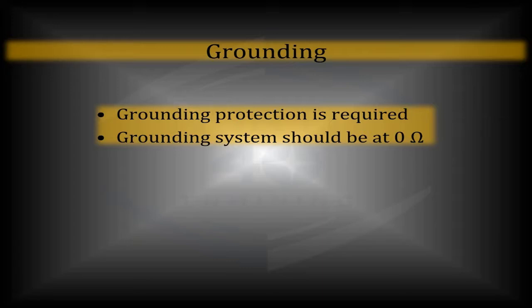Now, there's a difference between a grounding path and an effective grounding path, and if you don't know the difference between those two, that's why you should defer to an electrician in dealing with some of this stuff. The effective ground path is one you put in there on purpose that is there as a preventative measure in case the metal parts do become energized. We want to make sure they're connected all the way back to the breaker panel so that way the breaker trips. If we have a break anywhere in there, there's a possibility, and I know as mechanical guys you've felt this before, that the conduit or the box could become energized and never trip a circuit. It just sits there and it's powered up and it generates heat, which could lead to a fire, but oftentimes it leads to shock, and it's to one of us. We've felt that before.